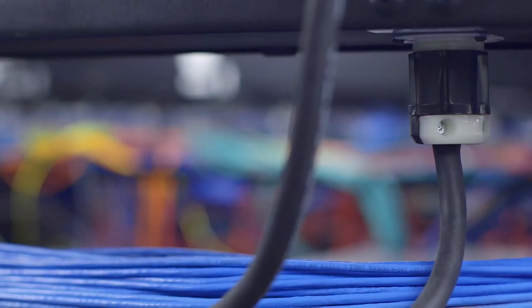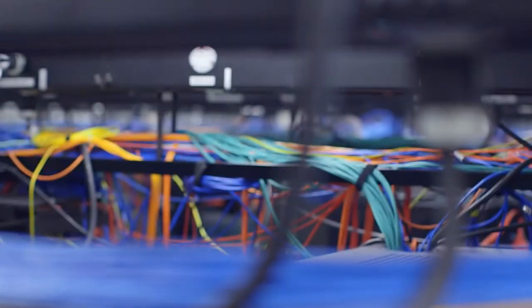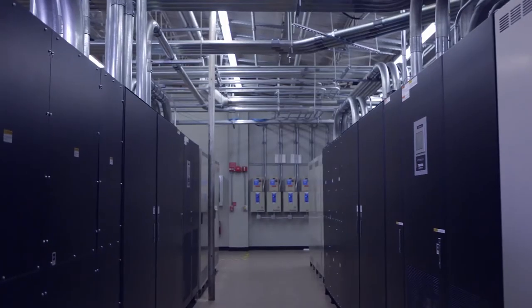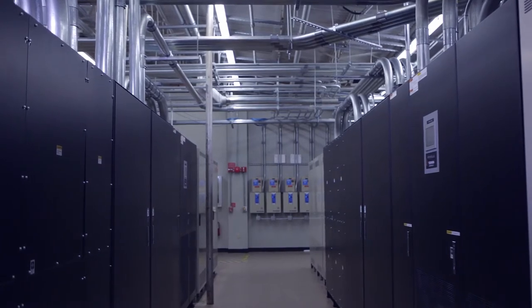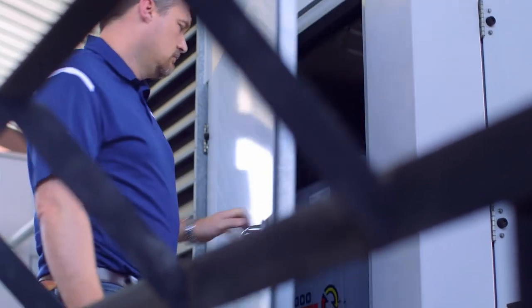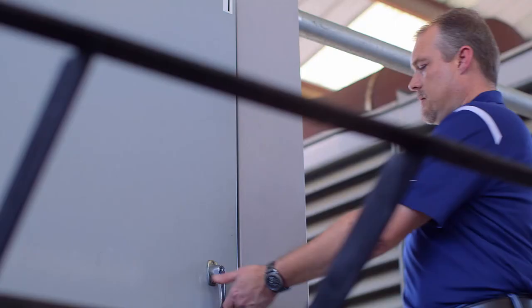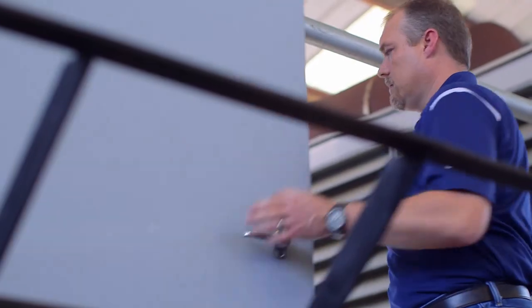In BTR1, we bring redundant power to every rack in the facility. Every rack has redundant power distribution units that are fed from redundant breaker panels. Those are fed from redundant UPSs, and then those are backed up by a redundant generator plant.